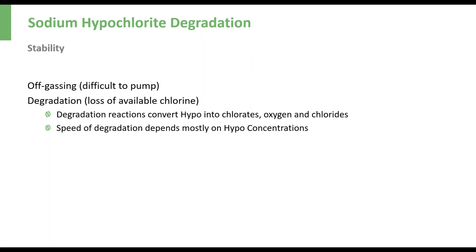So if you have a tank that has, let's just say, half the tank left over and it's degraded down, you put fresh sodium hypochlorite on that, that degradation rate is going to accelerate because you have degraded chemical blending with new chemical, which will dilute it, but it'll also accelerate the degradation.